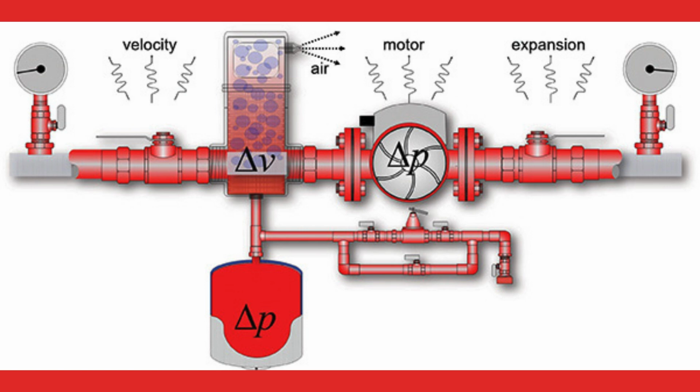3. Imbalance of moving components. Imbalance in rotating components like fan blades, flywheels, or compressor rotors can cause excessive vibrations, leading to premature wear, noise, and potential damage to other components. Regular balancing of rotating parts is crucial for maintaining system stability.